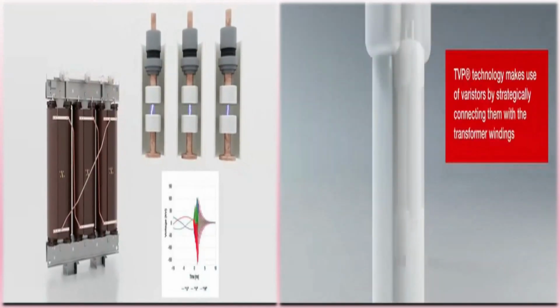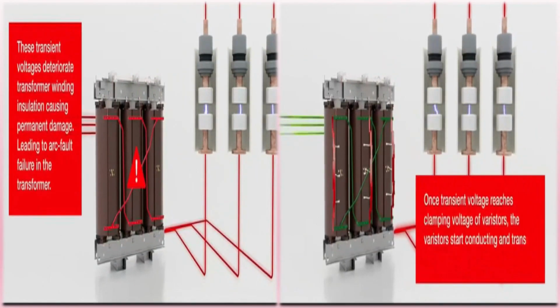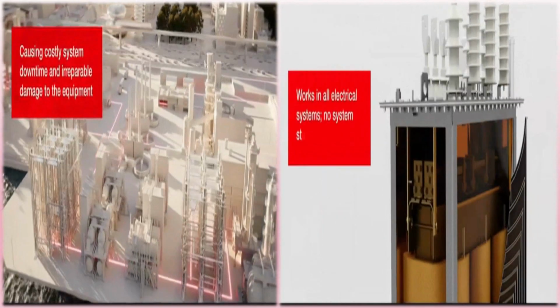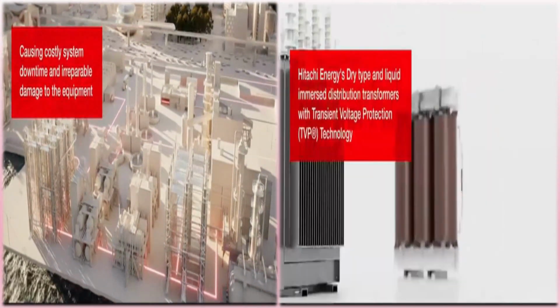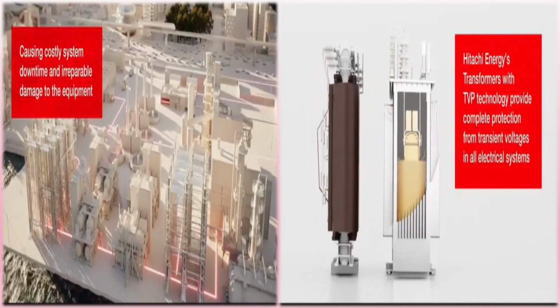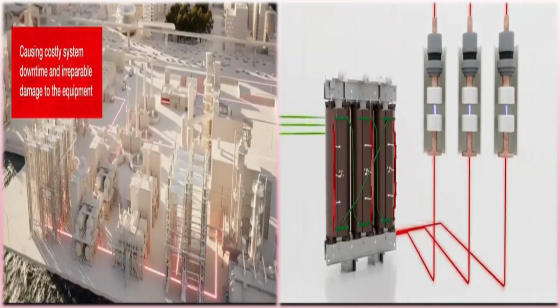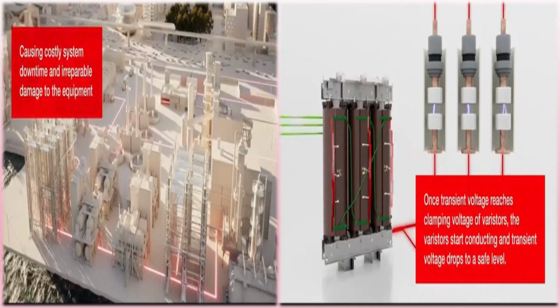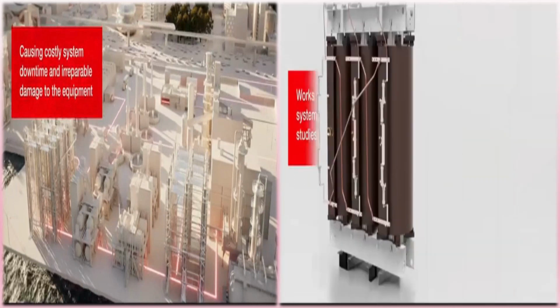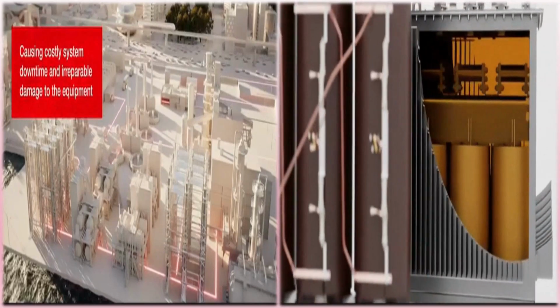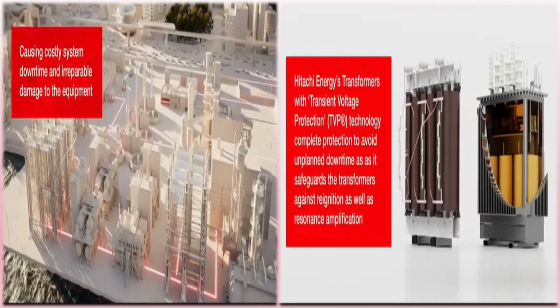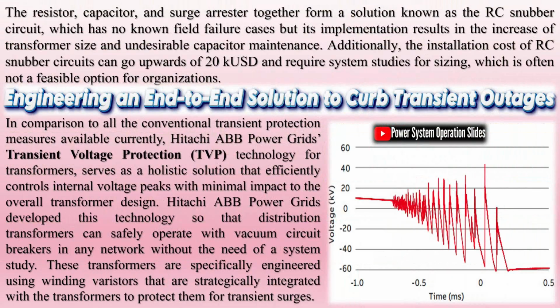Some of the more threatening network characteristics that increase the risk of switching transient damage include less distance between the transformer and circuit breaker, high upstream capacitance, switching of inductive load, and switching parameters of the circuit breaker. Currently, several surge protection measures exist to safeguard the primary winding of a transformer from VCB-induced transient outages. However, they do not either offer complete protection or are too expensive for installation and regular maintenance. For instance, surge arresters provide basic protection from overvoltage stress to ground by restricting the voltage peak of the transient voltage waveform, but do not provide any significant phase-to-phase protection.